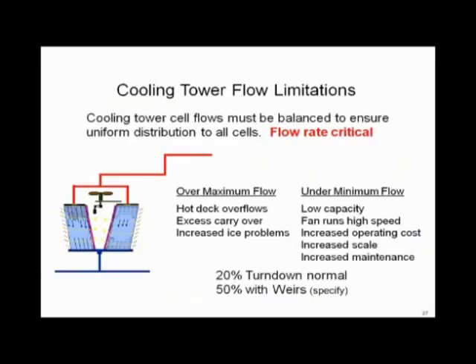Flow limitations on cooling towers are an interesting question — and the answer is yes, they are real. Looking at a typical cooling tower cell, are flow rates critical? Yes, and a lot of people ignore this. There is a maximum flow through every tower, and if you exceed it, water goes over the hot water basins and floods down the outside of the tower — wasted energy, wasted chemicals.